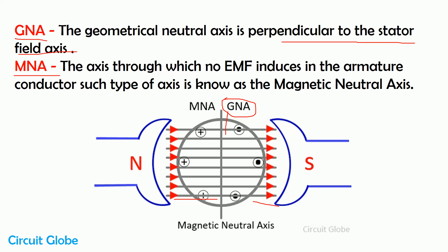The axis where no EMF is induced in the armature conductor is known as the magnetic neutral axis. And as there is no EMF induced in that line, we place our brushes and commutator in that axis. Here you can see this is the magnetic neutral axis of the DC machine — brushes are safe and not getting damaged because there is no EMF in that axis.